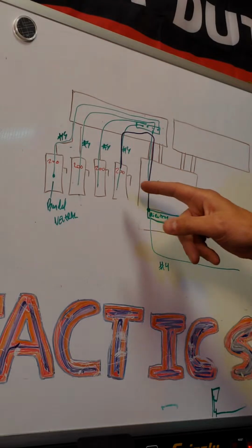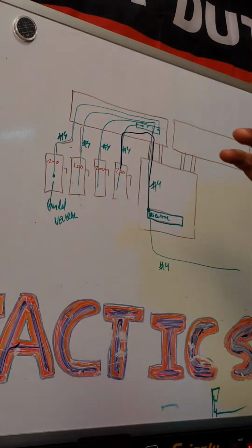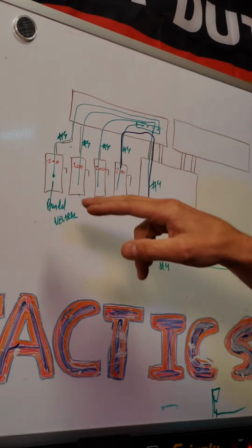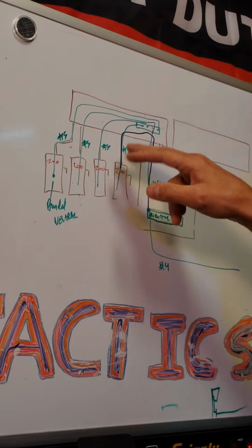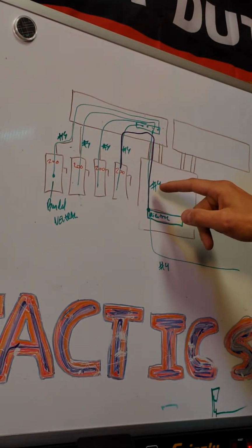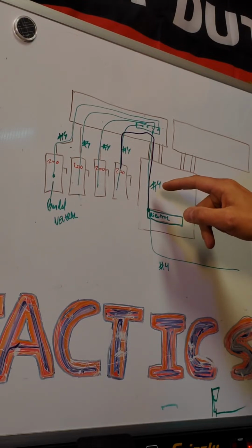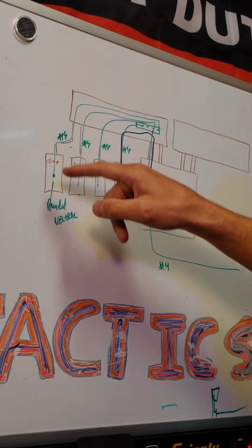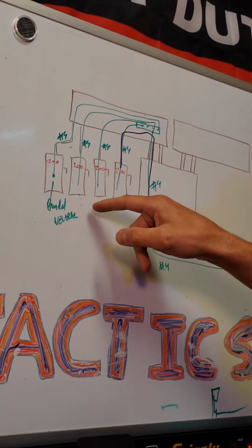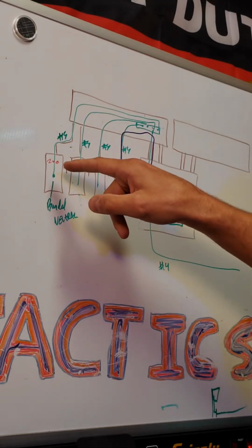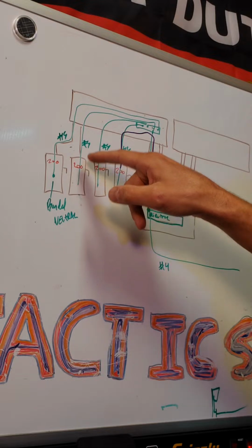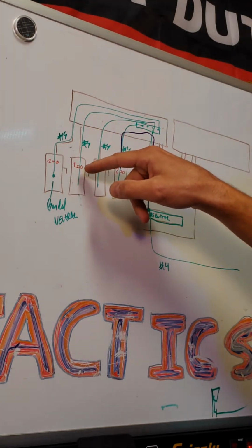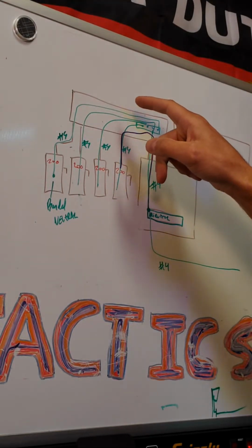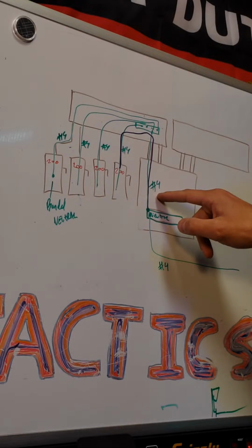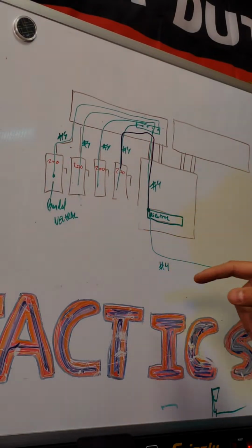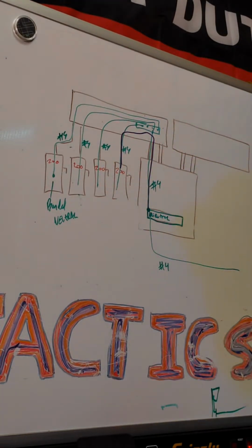And let's just entertain the thought of 20 amps on this neutral, 20 amps here, 20 amps here, 20 amps here. You got 80 amps in neutral here. Better yet, let's get a fault on some pipe catastrophically where we need to clear the fault of pretty much 500 kcmil of wire at the same time on a number 4. So it's really, really easy to mess this up.